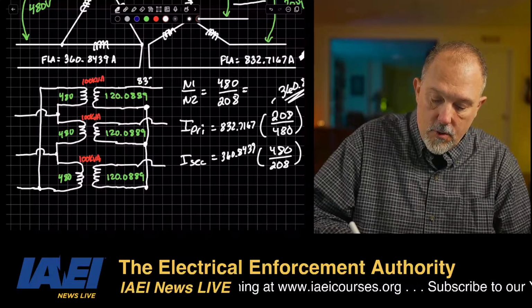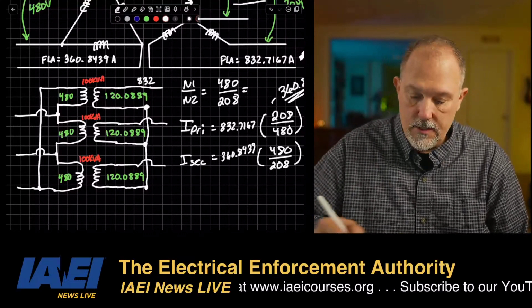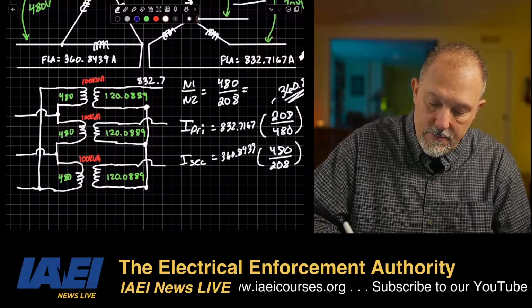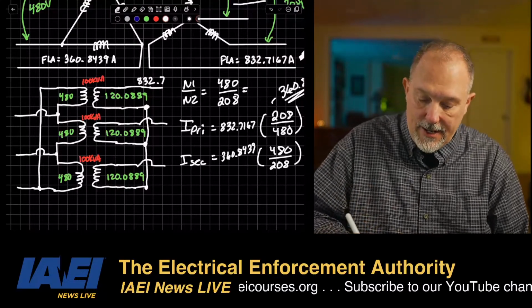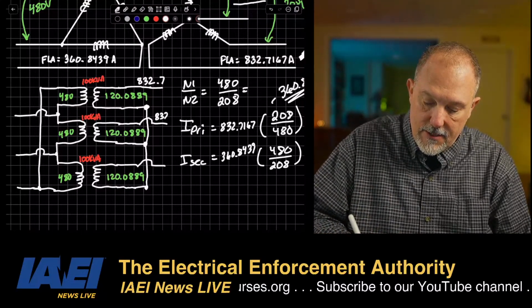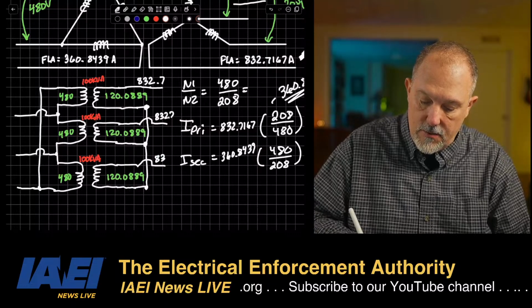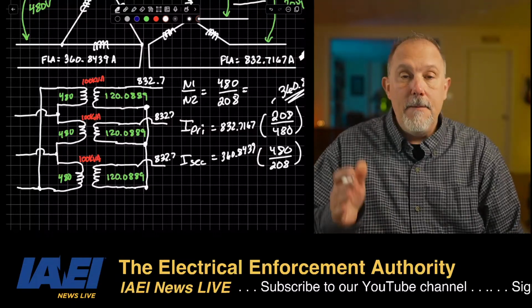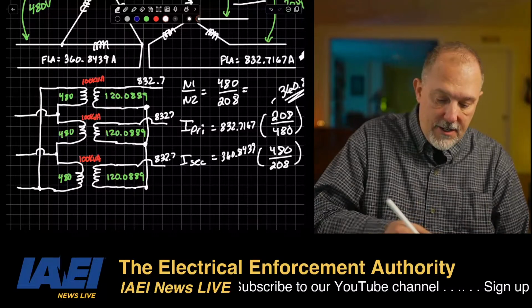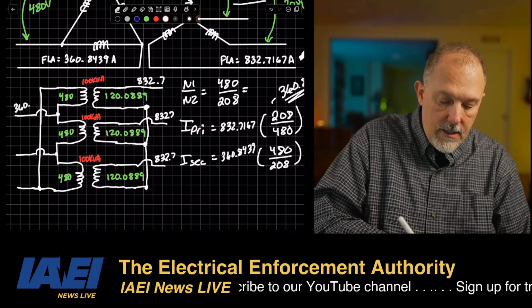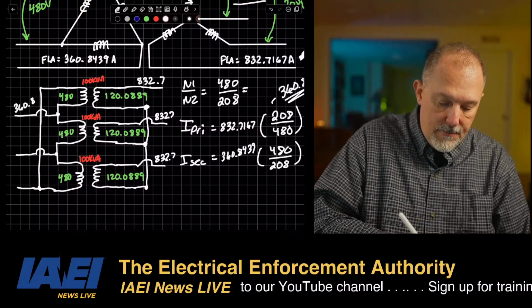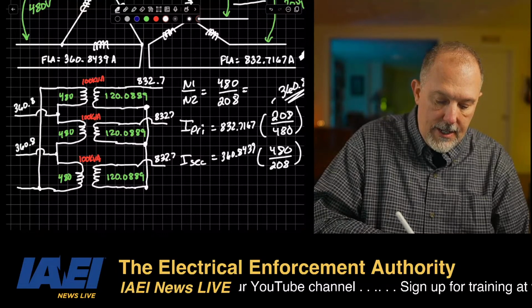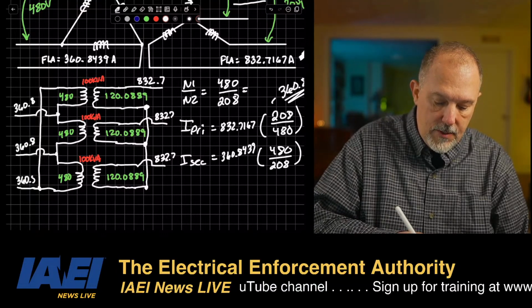Now what I did was I calculated 832.7 on the secondary, and on the primary, I calculated 360.8.